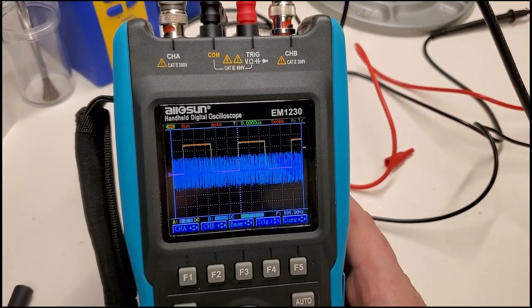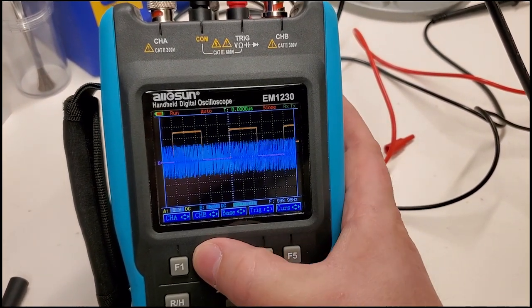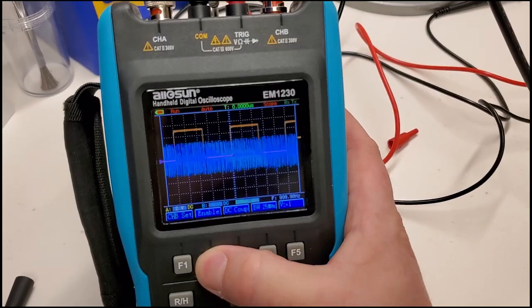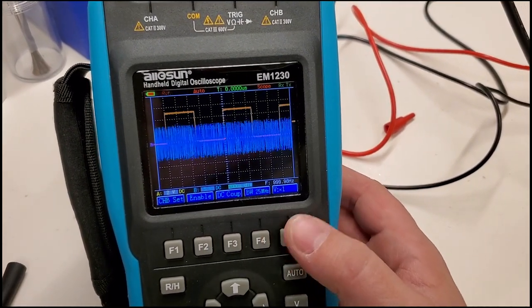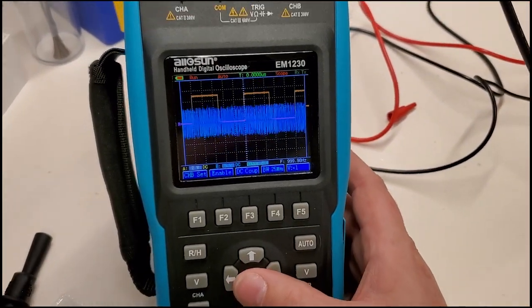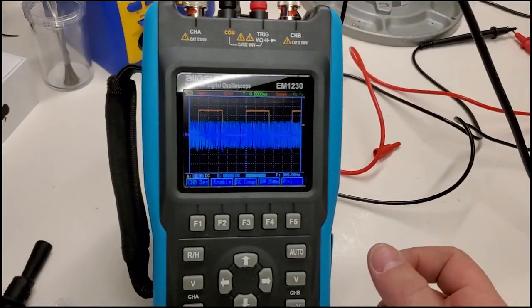I'm going to give it some bipolar energy and I'm going to drop the trigger down and we're going to put out channel B. You can see all the different, you can change your coupling and stuff. Again, I am just experimenting with this meter. I haven't had it too long. I've just used it for displaying some of my waveforms from a couple of electrosurgical generators.